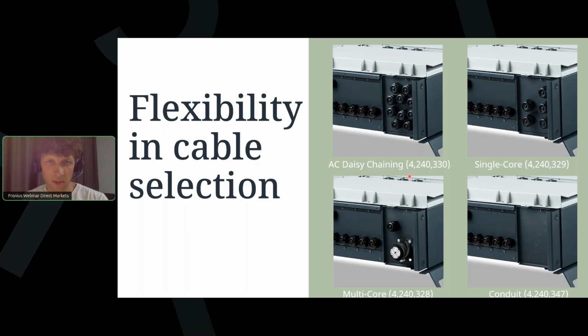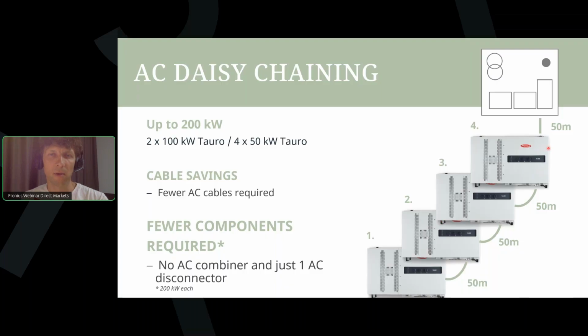What is AC daisy chaining? It means you can put just one AC cable, connect it to one inverter, and then connect other inverters in a chain, up to four 50 kilowatt inverters or up to two 100 kilowatt power inverters. So you can have up to 200 kilowatt power of inverters with just one AC cable from the main switchboard, for example. This way you save on cables or disconnectors.